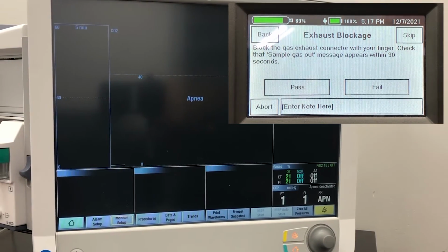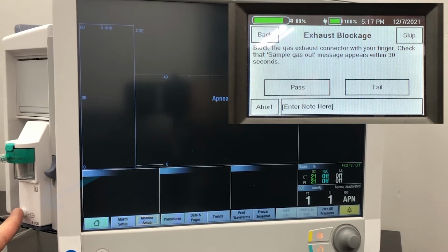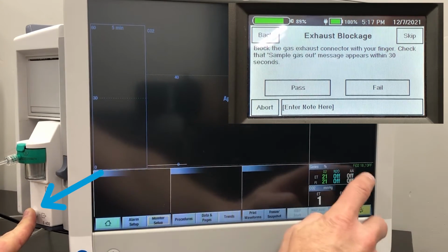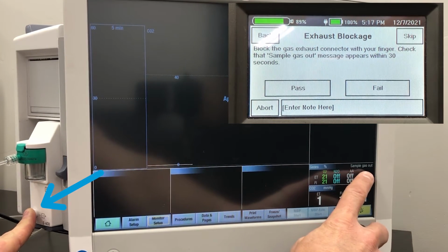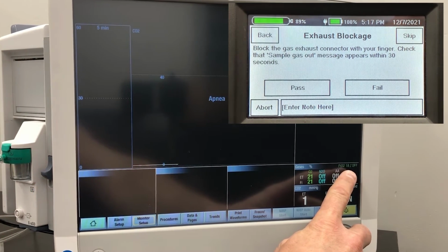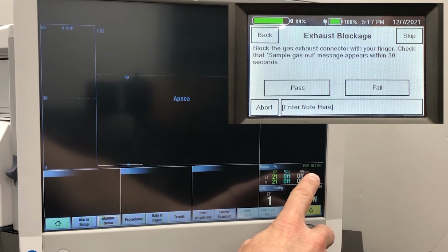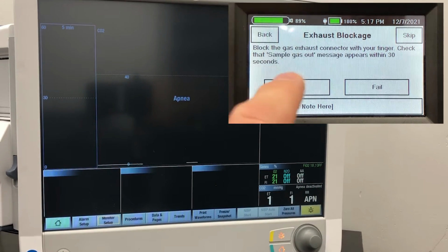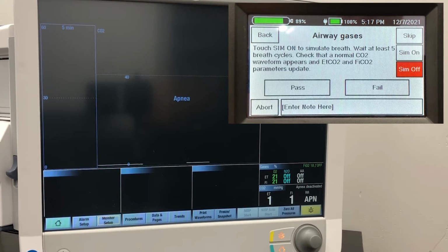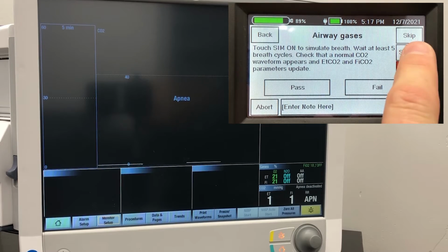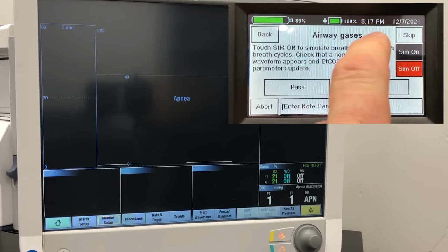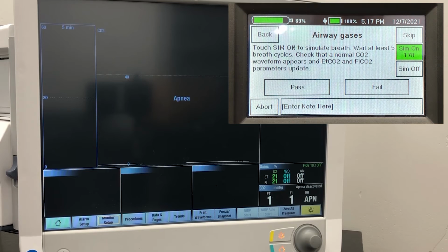We do that by using our finger to block the exhaust port on the front of the module. And we watch over here for a message, sample gas out. See that happen pretty fast. And we can let that off and it'll return to normal. So that's a passing result. Next, we're going to simulate breath. When we touch sim on the SmartTank, we'll start simulating a CO2 waveform very similar to patient breathing.